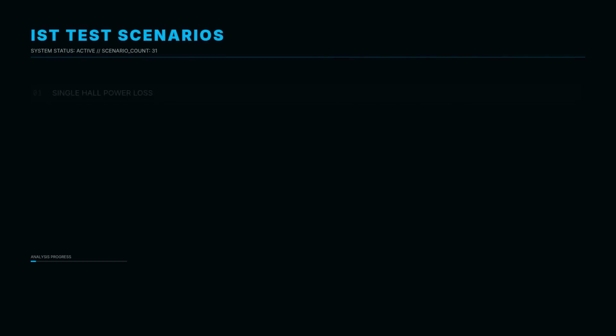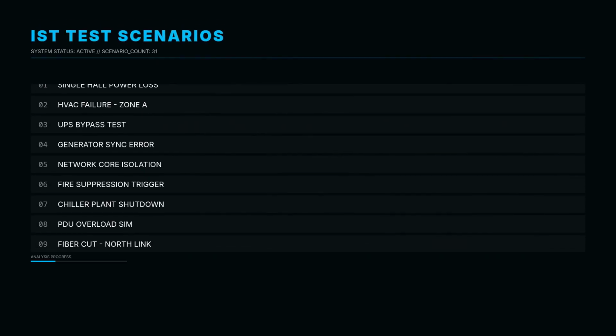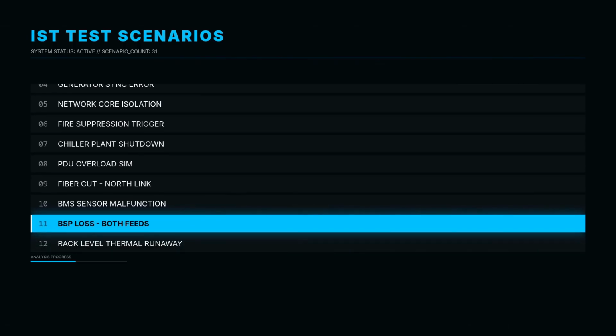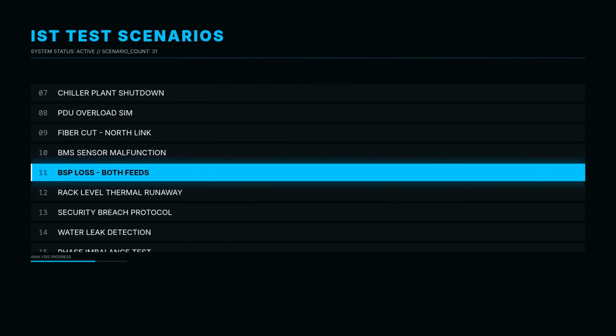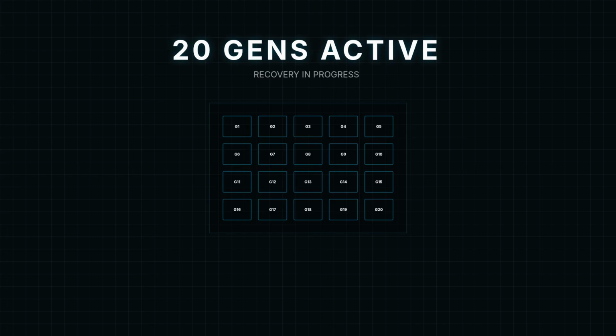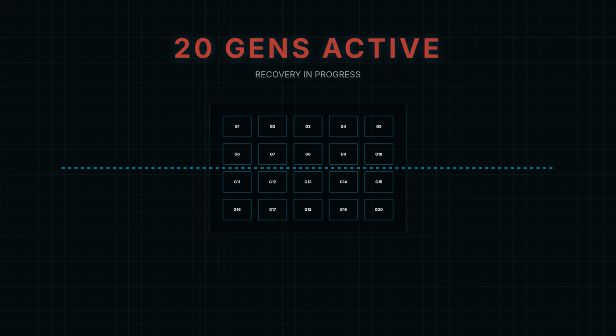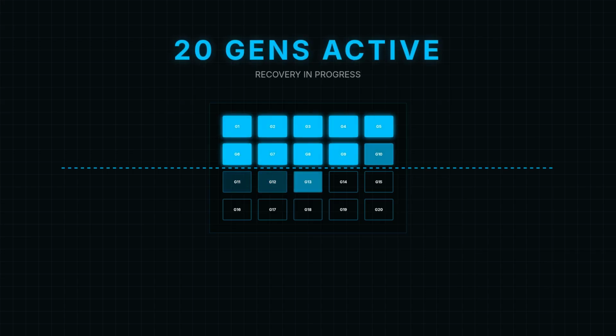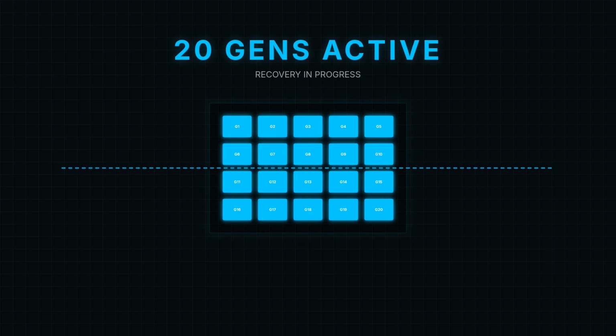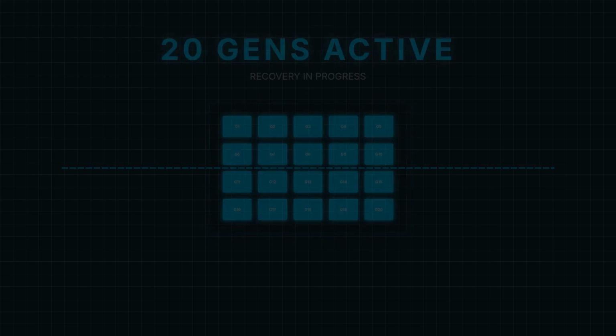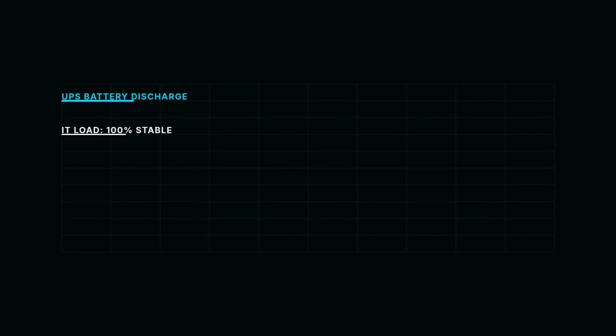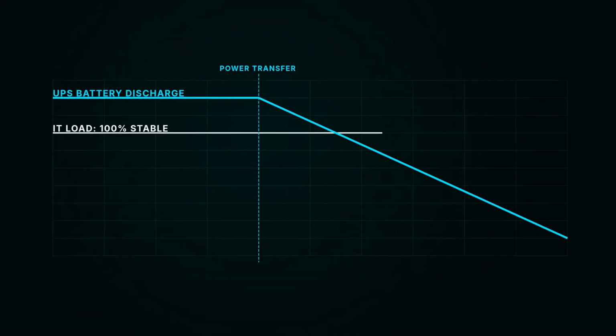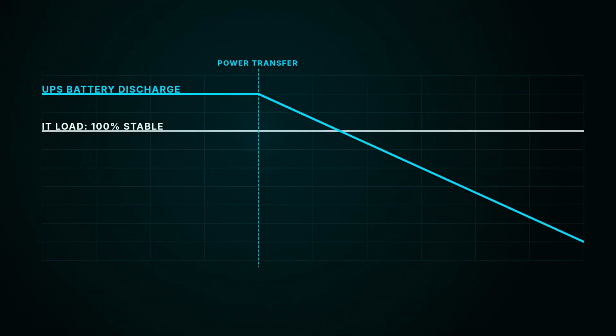Over 6 weeks, we execute 31 test scenarios. These range from single hall events to campus scale failures with no single building equivalent. Scenario 1, total BSP loss. We trip both incoming feeds. All 20 generators must start within 10 seconds to restore campus power. All 4 hall UPS systems must support the IT load from battery through the transfer. We verified 0 IT load interruption across the campus.